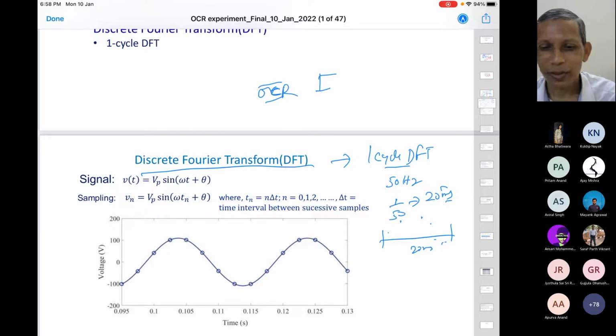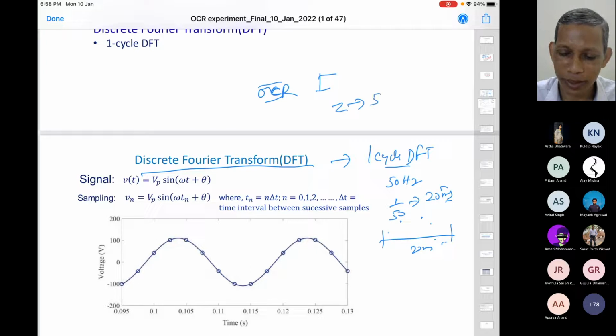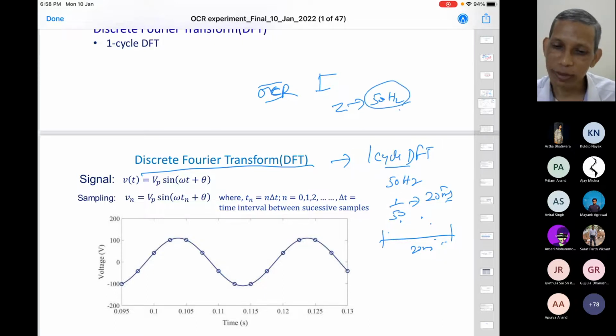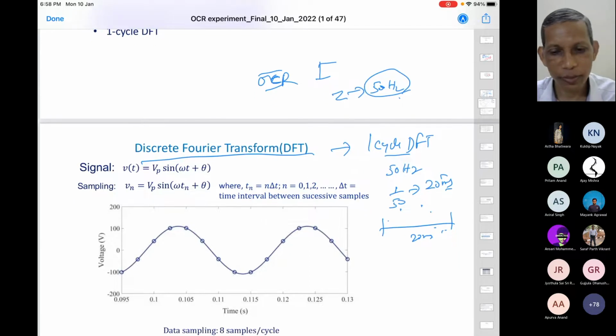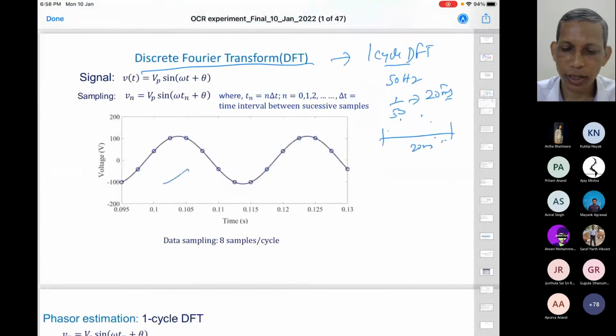But our analysis and design of the protection system is based on the impedance-based perspective, meaning it is the fundamental, 50 Hertz. When you take a distorted wave and take the RMS value, that is not correct, because decaying DC will be there. If you get the corresponding 50 Hertz component, it will be in accordance with your design philosophy, and the decision process will be more accurate. That is why even for the overcurrent relay, today's numerical relay does this fundamental extraction. So this is about the signal samples.